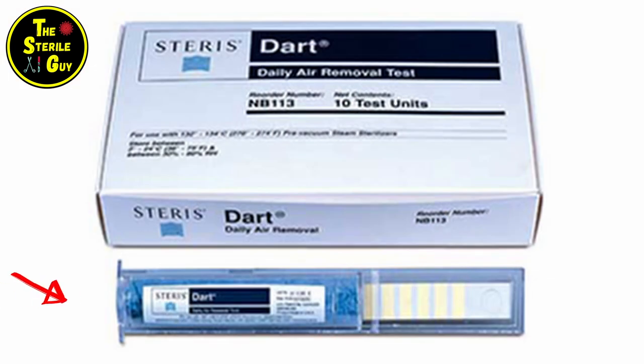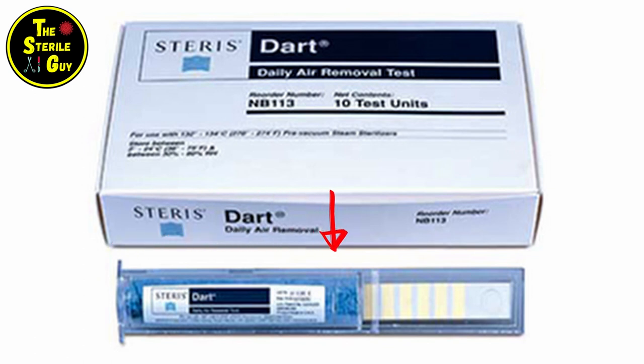The DART test is actually a completely different construction and is trademarked by Steris. DART — D-A-R-T — stands for daily air removal test. Here is the DART test. On the far end of the cylinder portion is a very small entrance where air and steam make their movements. Inside the cylinder is stuffed wrap that makes it challenging for air and steam to penetrate and be removed — it mimics a wrapped tray, acting as both a barrier and a challenge for steam to penetrate.